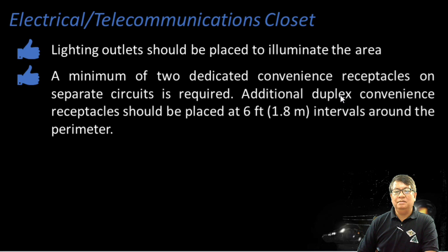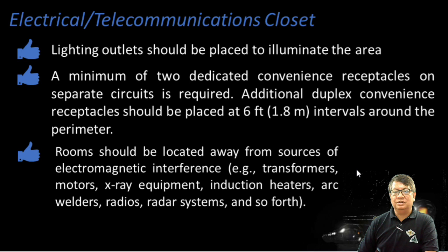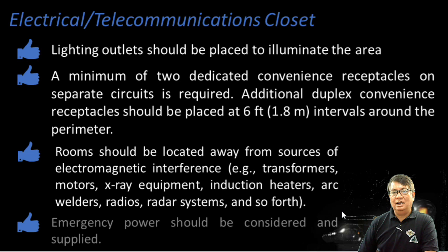Okay, a minimum of 2 dedicated convenience outlets or receptacles on separate circuits is required. Your room should be located away from sources of electromagnetic interference. Kasi po, telecommunications ito eh. Baka hindi na maganda yung reception. So, we need to put away these like transformers, motors, X-ray equipment, induction heaters, welders, and other radio and radar systems. Okay, para walang interference, no?